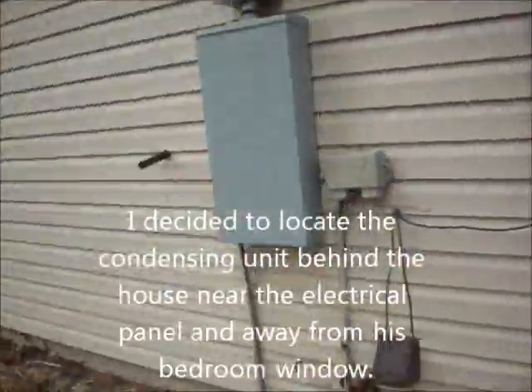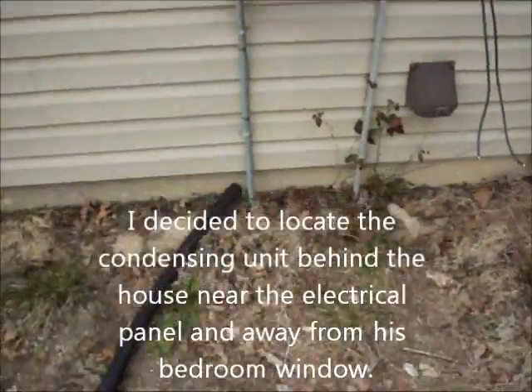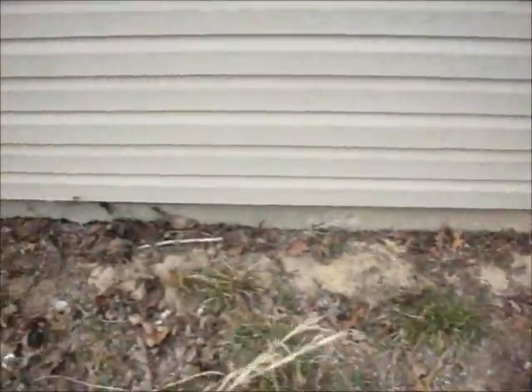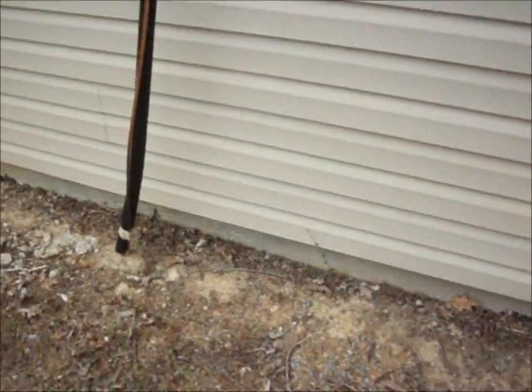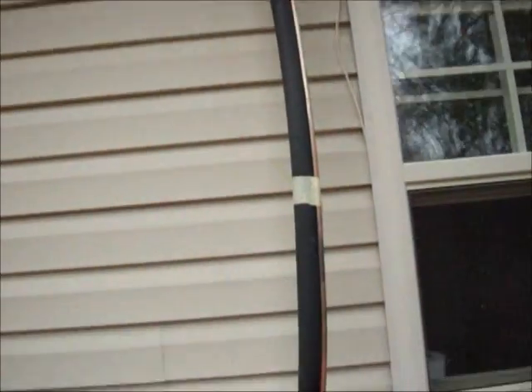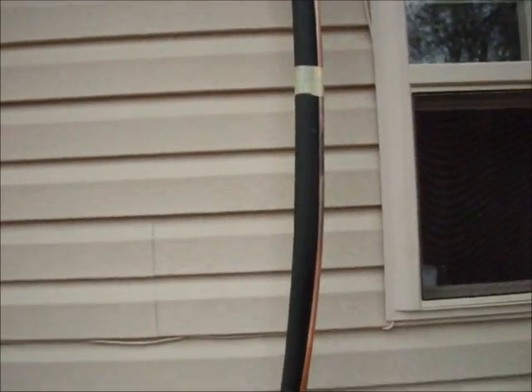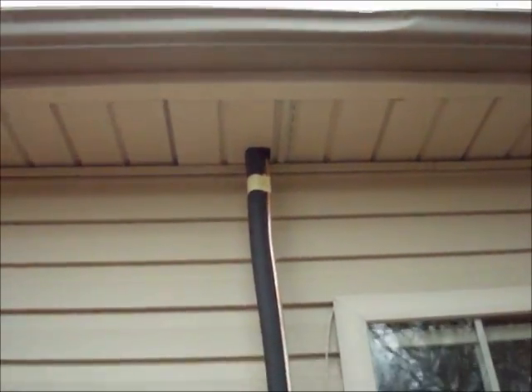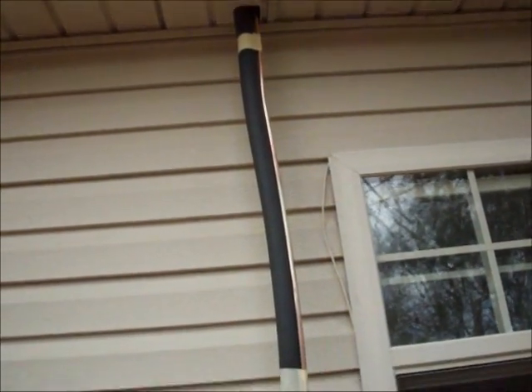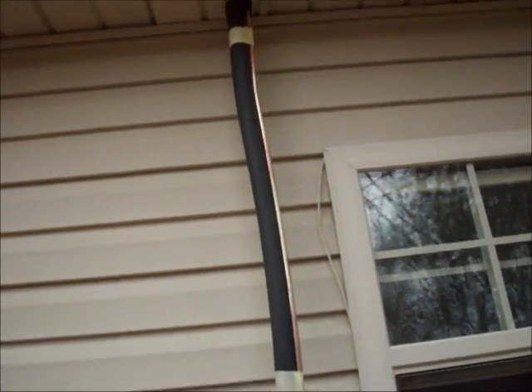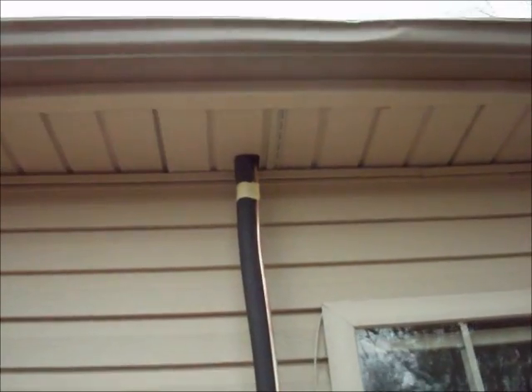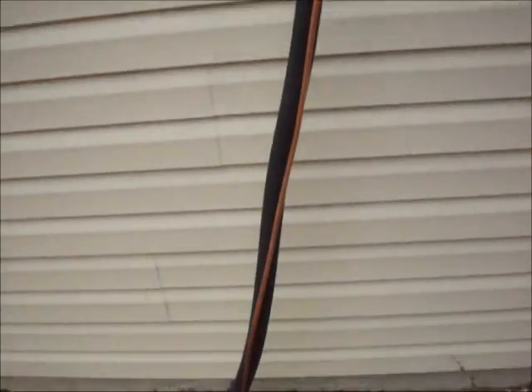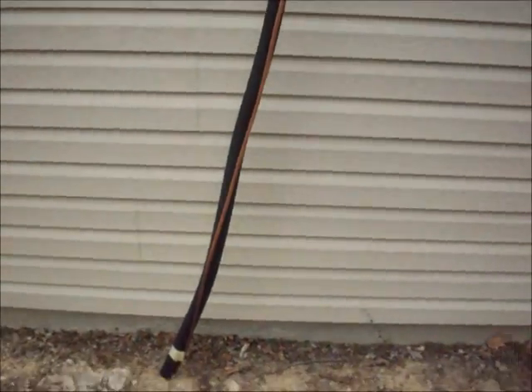I've got to come out of my electrical panel box with conduit down into the ground and run it across to where the refrigeration lines run overhead, and run my 6-6-8 in conduit up the side of this into the attic and over and down into the closet you just saw, then box everything in with some sheet metal and paint it to match the siding so it's not as obtrusive.